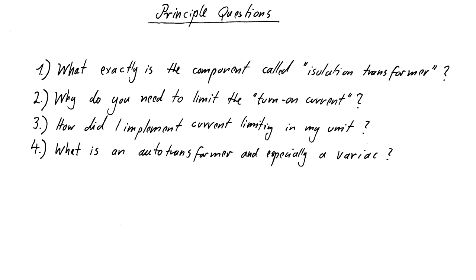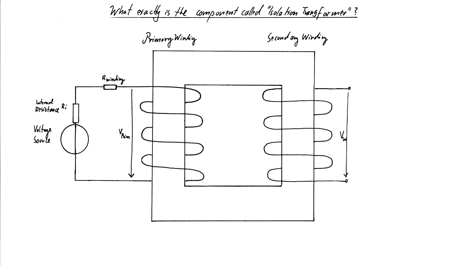So let's come to question 1. Per definition, an isolation transformer is every transformer equipped with at least one primary and one secondary winding. The 2 windings must not be connected with one another, and the secondary must be able to deliver a voltage that is isolated from the primary voltage. That means no defined voltage exists between any point on the secondary with respect to any point on the primary winding. In theory, this is true for most transformers you will ever see.